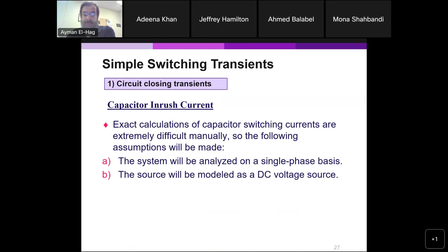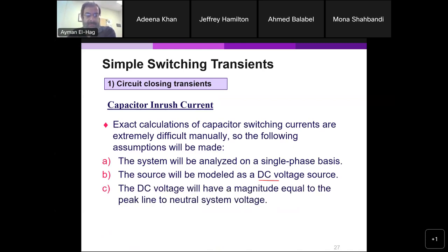The source will model it as a DC source, not as an AC source. The DC voltage has a magnitude equal to the peak line to neutral. So this DC voltage that we'll assume has a peak value equal to the line to neutral system voltage, and we ignore the resistance.